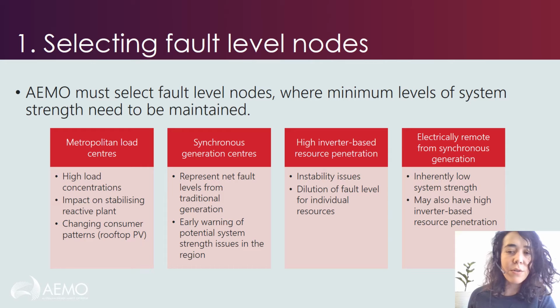We choose to create for each region in the NEM at least one fault level node which is at a metropolitan load centre, one which represents kind of the centre of synchronous generation, which is contributing to fault levels. And also as levels change at this area, we consider them to be an early warning of system strength issues in the region. We choose one which has, at least one, which has a high penetration level of inverter-based resources, and also one that represents areas where the section of the network is electrically remote from synchronous generation.